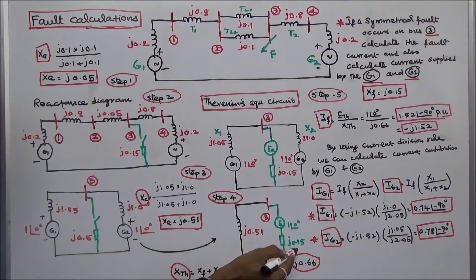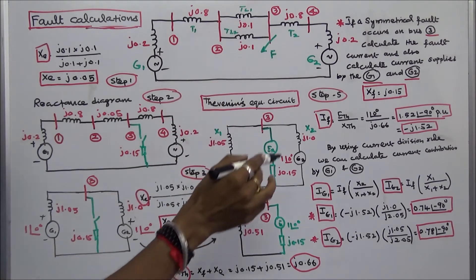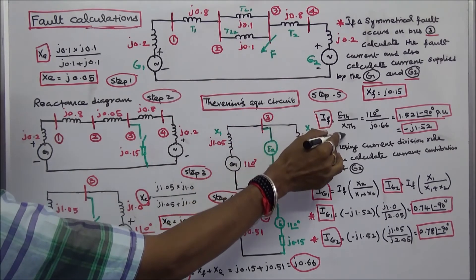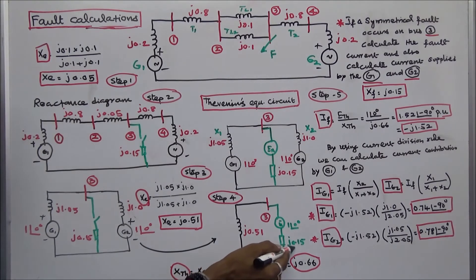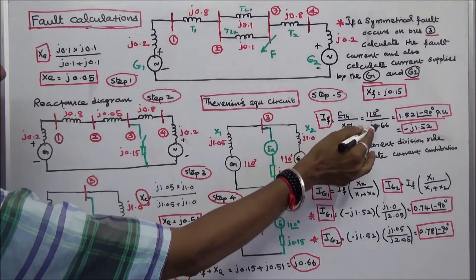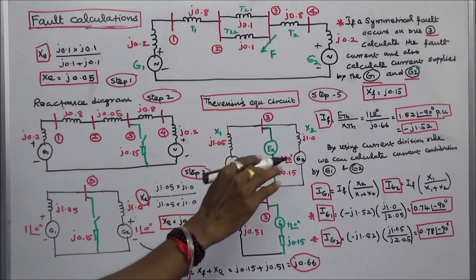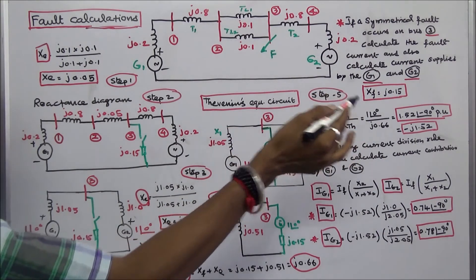The fault reactance is J0.15. Step 5: calculate the fault current IF. Fault current IF equals E-Thevenin divided by X-Thevenin. X-Thevenin equals the fault reactance plus the effective reactance: J0.15 plus J0.51, so X-Thevenin equals J0.66. E-Thevenin is 1 angle 0 degrees. Therefore, fault current IF equals 1.52 angle minus 90 degrees per unit, or minus J1.52 per unit.